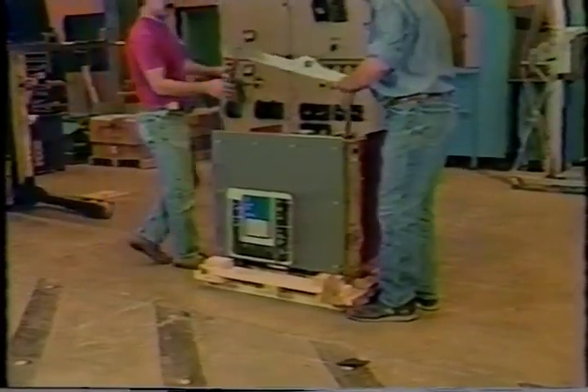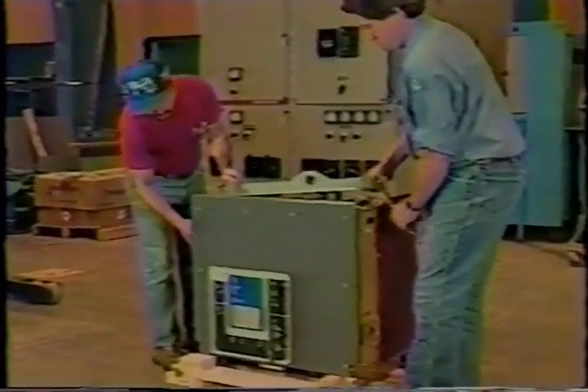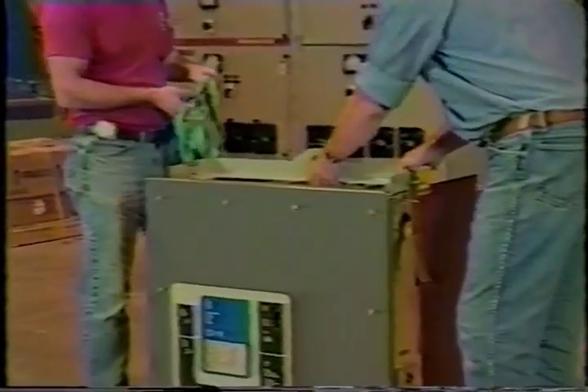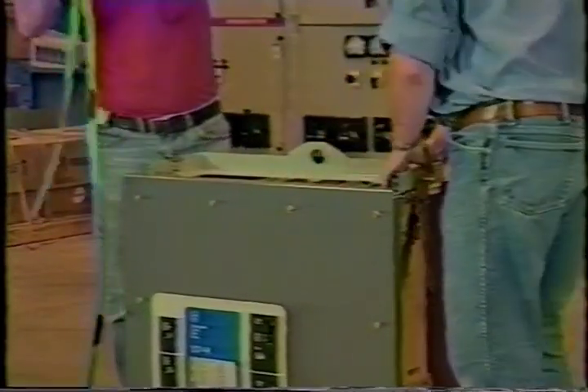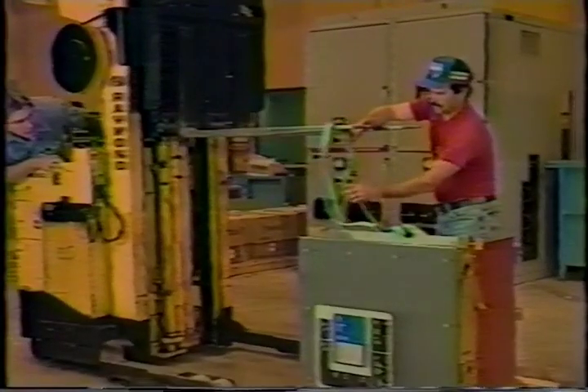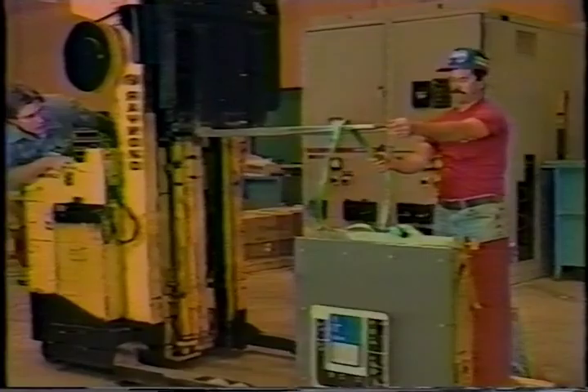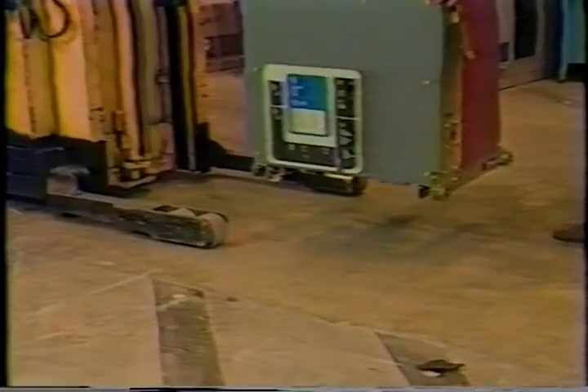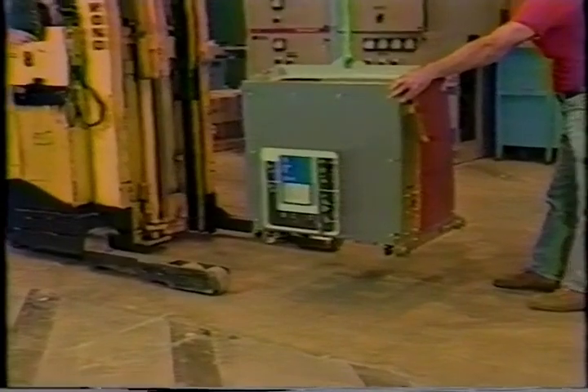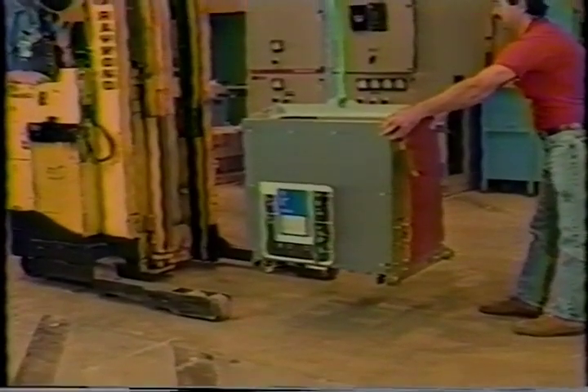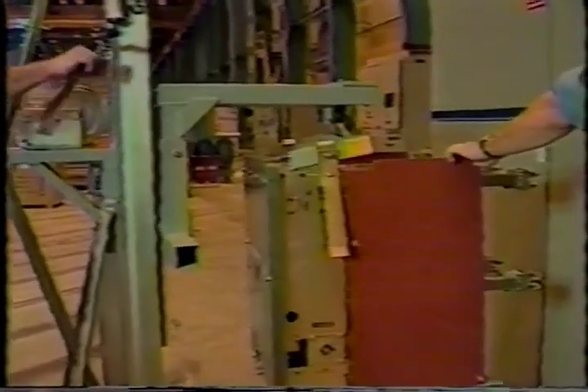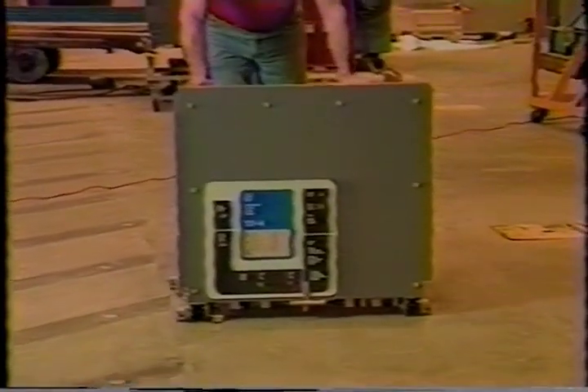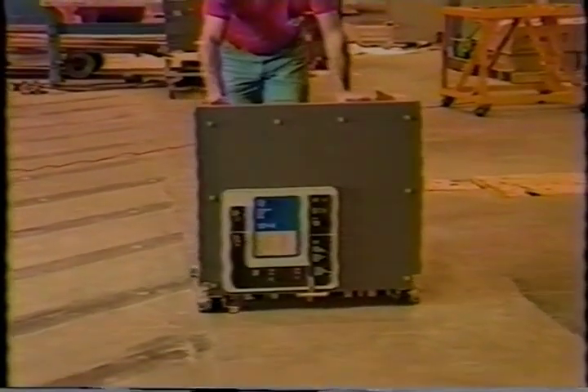A breaker lifting yoke is provided with each shipment. This assembly snaps on the top of a breaker to provide a means for attaching an overhead lifting device. Any device which can support the breaker weight and lift high enough to reach the extension rails may be used, such as an overhead crane or hoist or a forklift. In other instances, a portable lifter can be provided. This device should not be used to transport the breaker, merely lift it into position. The VCPW breaker can be rolled directly on the floor.